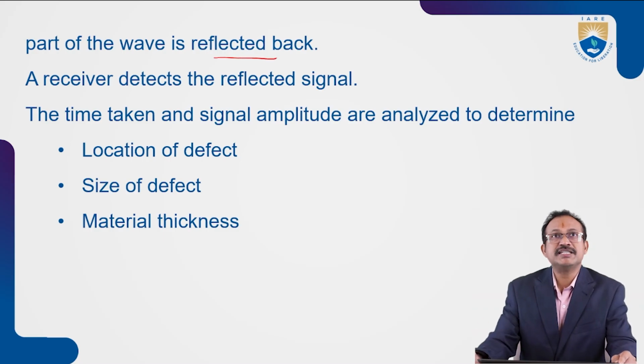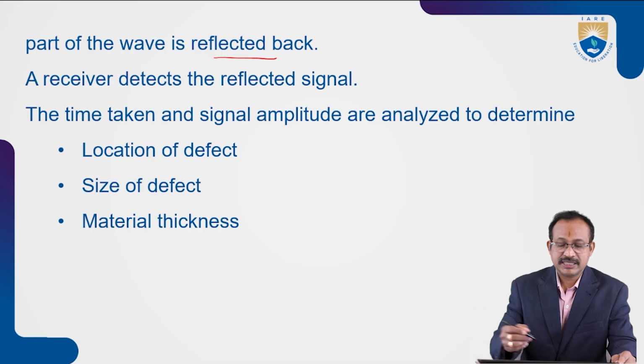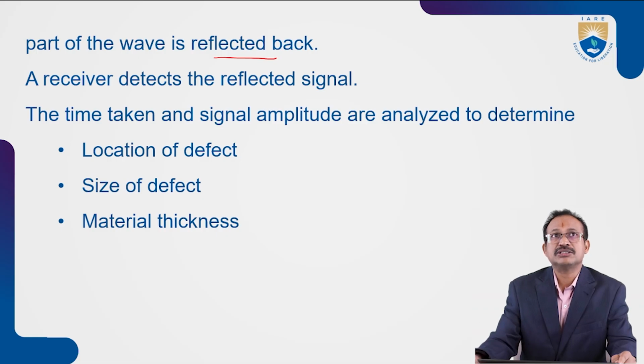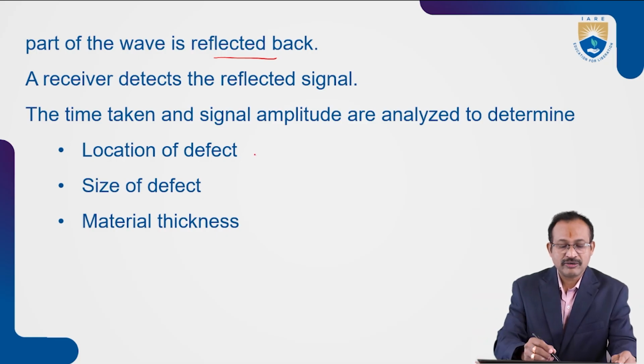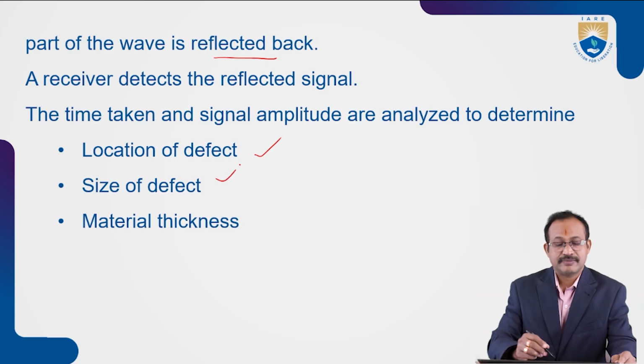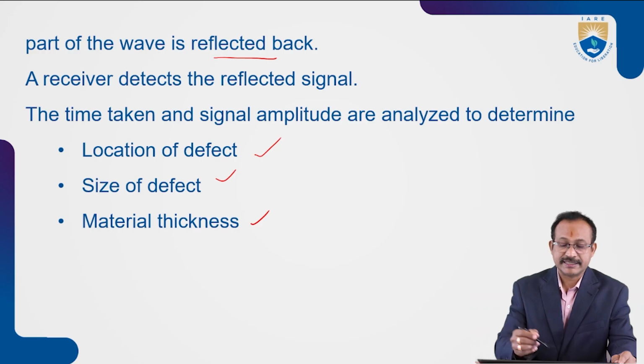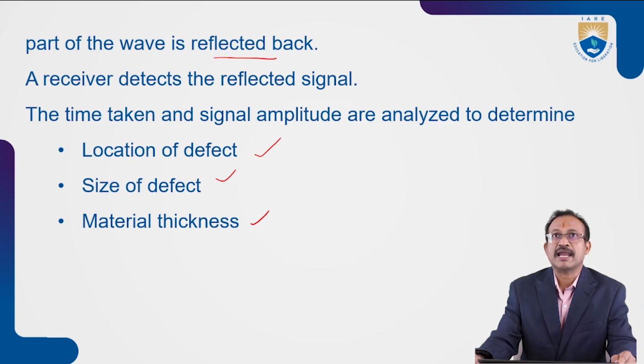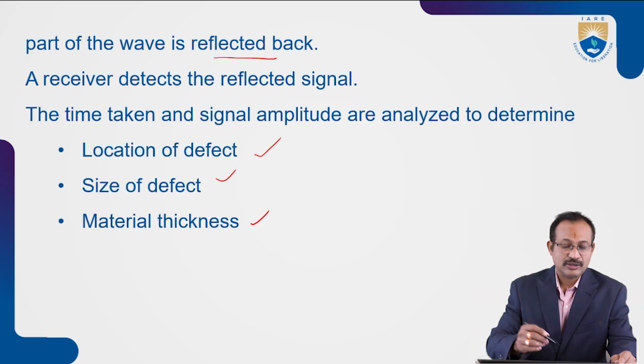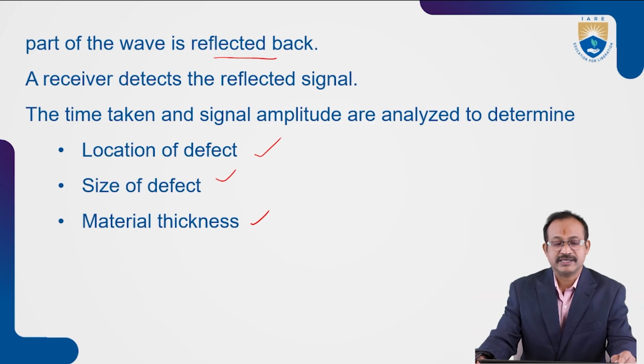A receiver detects the reflected signal. The time taken and the signal amplitude are analyzed to determine location of defect, size of defect and material thickness.